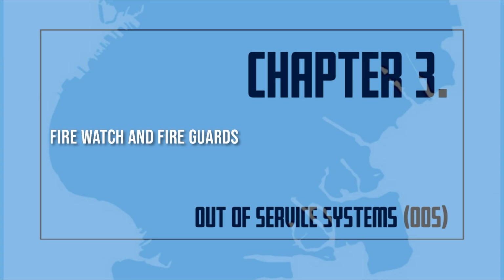Have no other duties. The fire watch for an out-of-service standpipe, sprinkler, or fire alarm system shall be maintained by one or more fire guards. The impairment coordinator or other building staff trained and knowledgeable in conducting a fire watch may conduct a fire watch in lieu of a fire guard during the initial 4 hours of a planned removal from service, or after discovery of an unplanned out-of-service condition, provided that the floor area in which the fire protection system is out of service does not exceed 50,000 square feet.